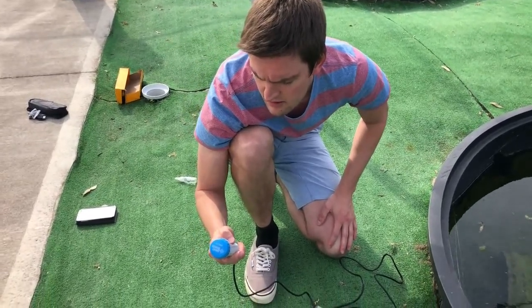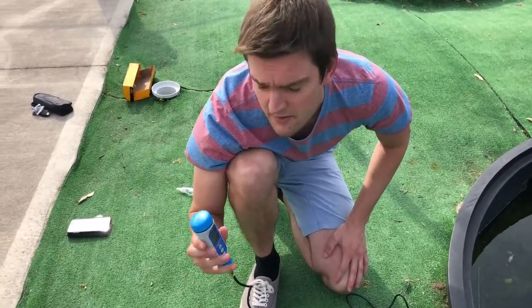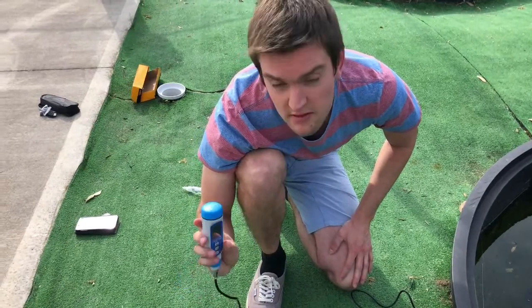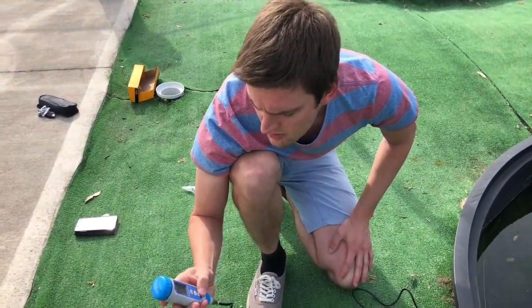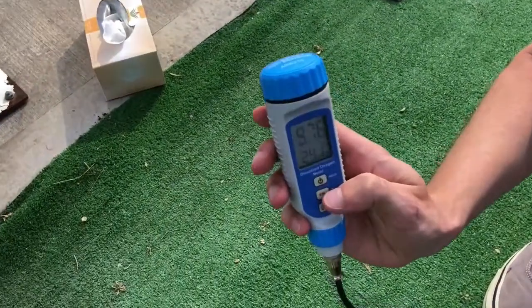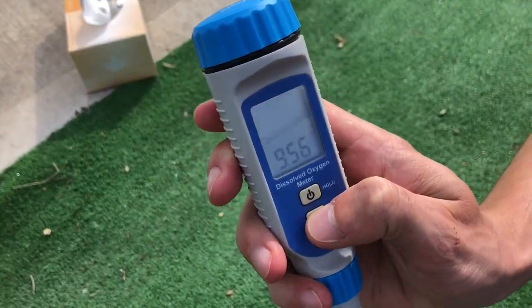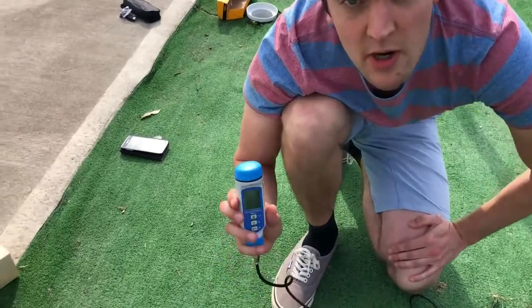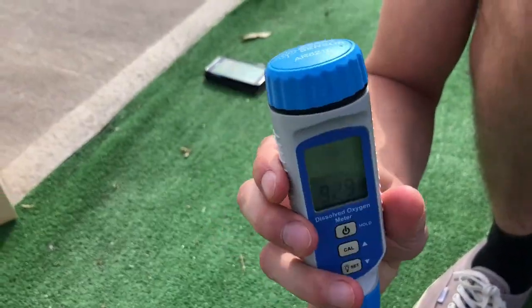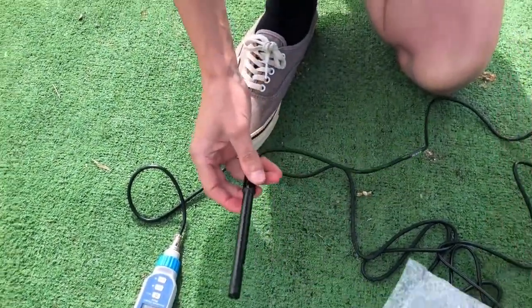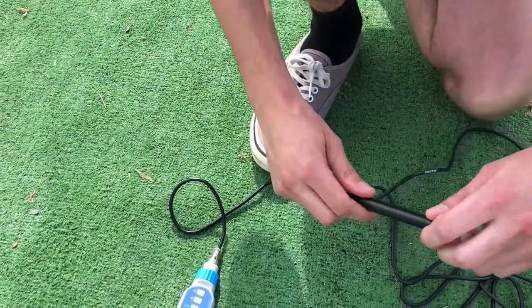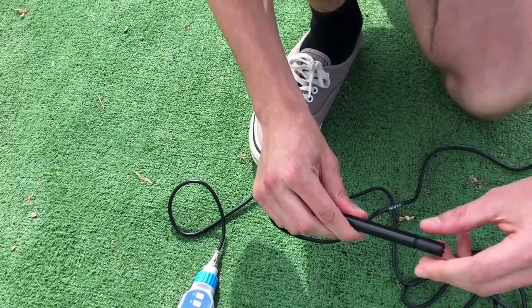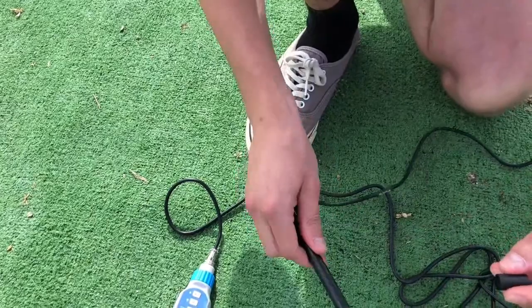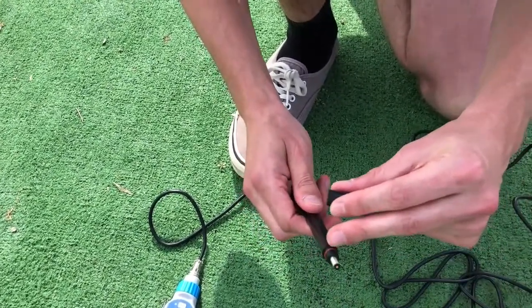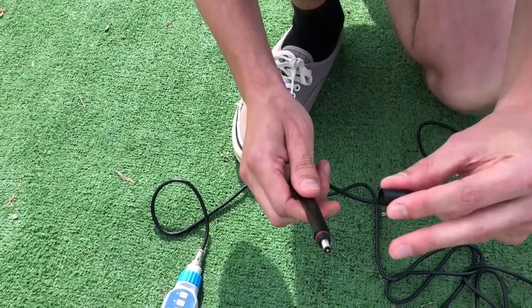Okay, so you need to calibrate the meter roughly every 2 to 3 months. So after the meter's been turned on, the second button down, which says cal, you hold that down for approximately 3 seconds and you've entered calibration mode. For the 0 point with the calibration, we need to firstly unscrew the probe head, and the probe head and the probe itself needs to be dry.